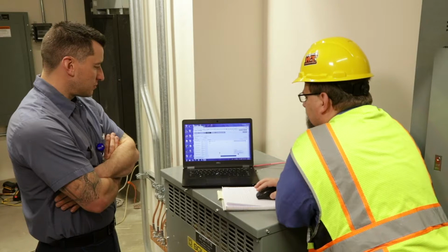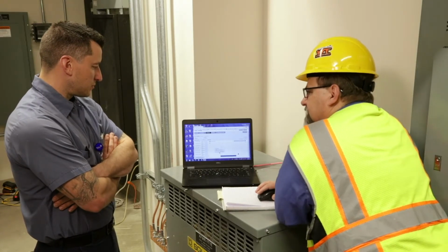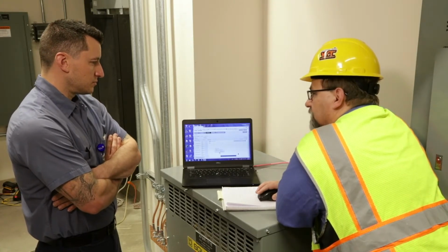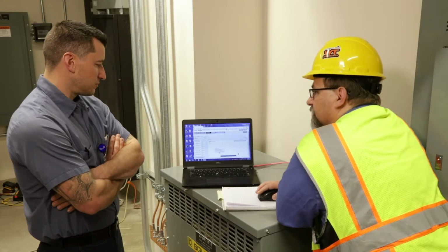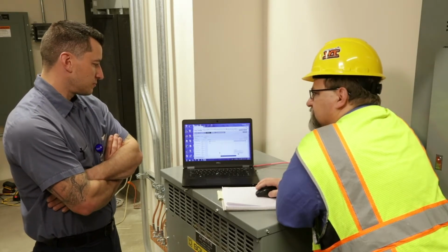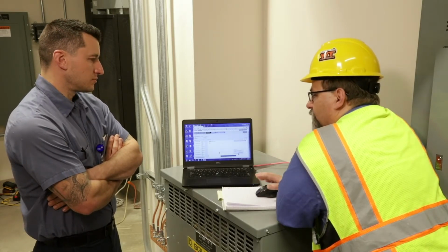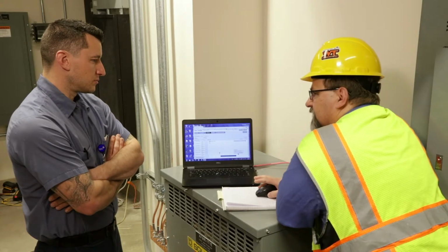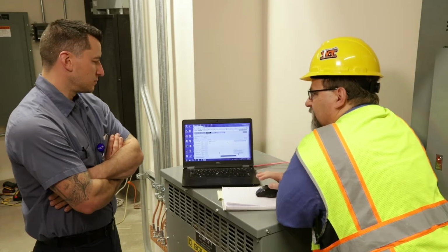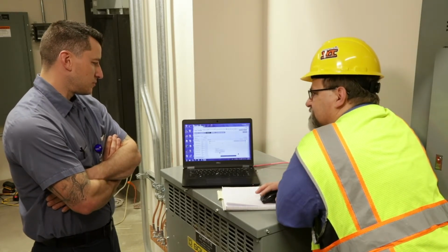And so during normal hours, our common areas, which we've designated as hallways and public spaces where we want to keep the lights on, because of the sensor, they'll only turn the lights on, they won't turn the lights off, right? Okay. After hours, it'll turn them on and off. And then if you hit the override, the button works for 2 hours, I think is what the setting is. And so after that 2 hours is up, the override goes away and the response to the sensor again turns off. Okay. So that way we save energy, but we also keep our public spaces on.